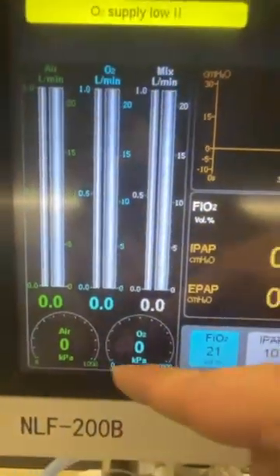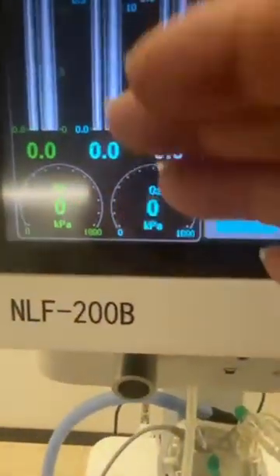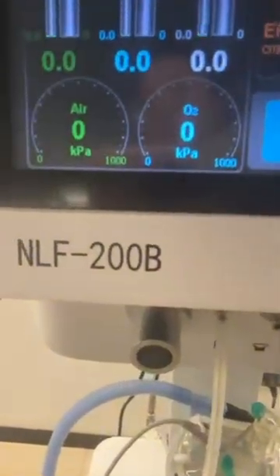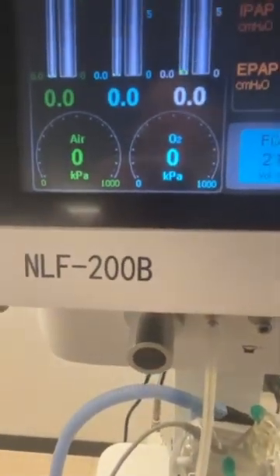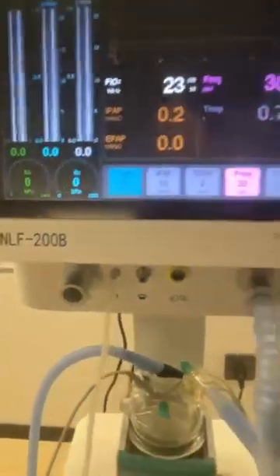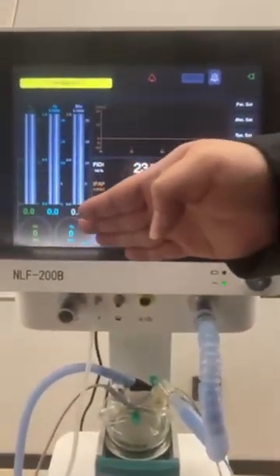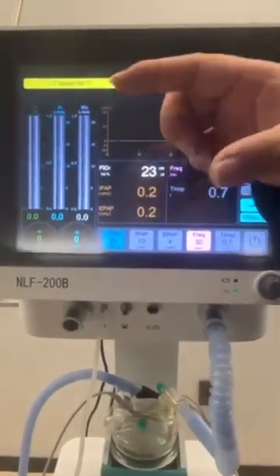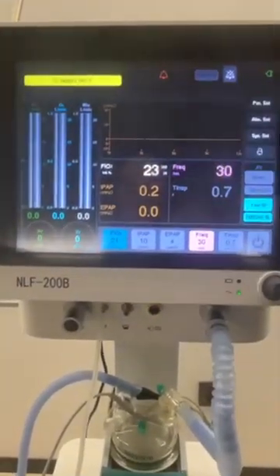And by the below side here, we can also show the pressure. This pressure means the inlet pressure. So sometimes if you don't know the inlet pressure of the oxygen source or the air source from the air compressor, you can just check here. We have the electric gauge. And for some other models, we are using the pressure gauge, which is the mechanical one.